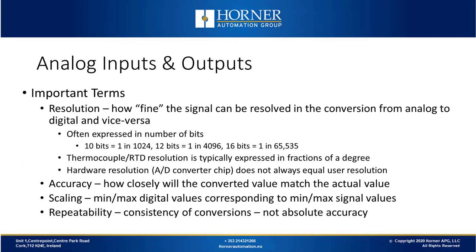The higher the number of bits, the more finely you can resolve that analog signal coming in. Sometimes resolution is expressed in AD converter resolution — maybe a 16-bit or 12-bit AD converter is used. However, the usable resolution passed on to the application is not always the full capability of the AD converter. Maybe you've got noise or instability issues and there's a round off. Accuracy is how closely the converted value matches the real value. With scaling, we're talking about the min and max digital values corresponding to the min and max analog values. And repeatability is the consistency of the conversions.